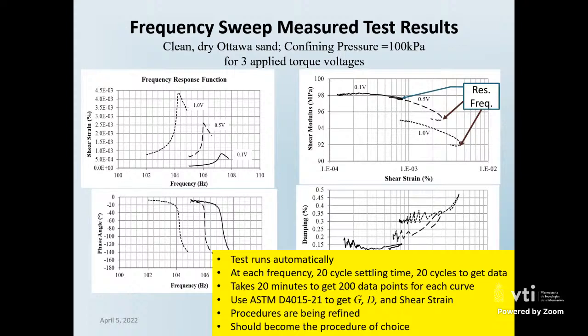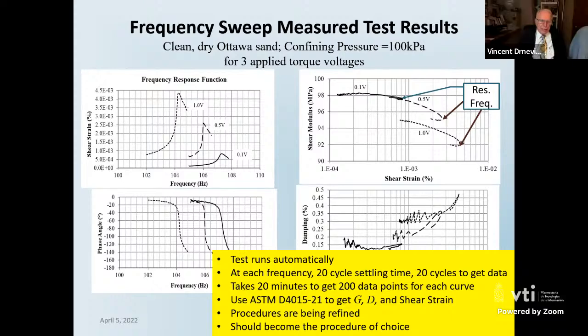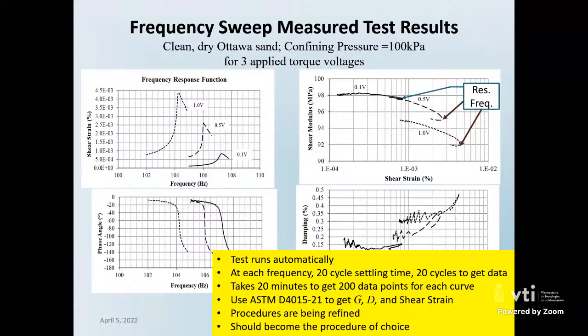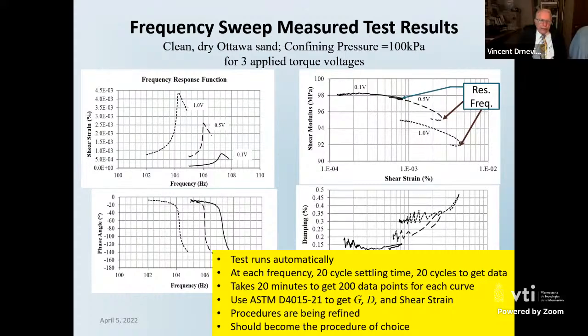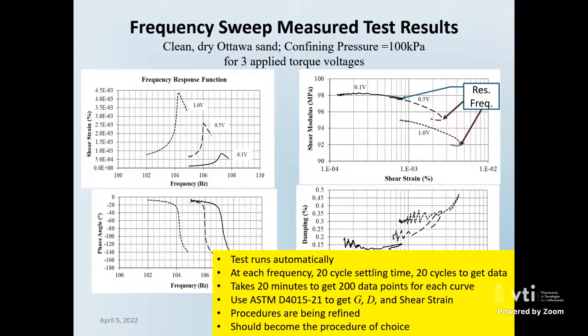Yeah, that's correct. But my point is, when you have a sample where some portion has some strain and another portion has a different strain, whether the response will be different. Because the level of strain affects the stiffness. That is what we are studying with this device. And the sample that you are testing has different levels of strain. That will be the effect. I fully agree that 0.4 or 0.3 are not really important. But my point is whether the differences in strain in the sample may cause some change in the measurements or the response of the material.